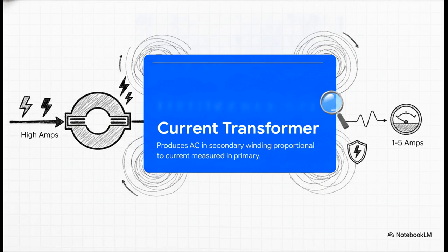It's a special instrument transformer designed to produce a safe, alternating current in a secondary winding, and that current is perfectly proportional to the massive surge happening in the primary line. Essentially, it safely steps thousands of amps way down to a standard output of just 1 or 5 amps, something a normal off-the-shelf ammeter can safely read.